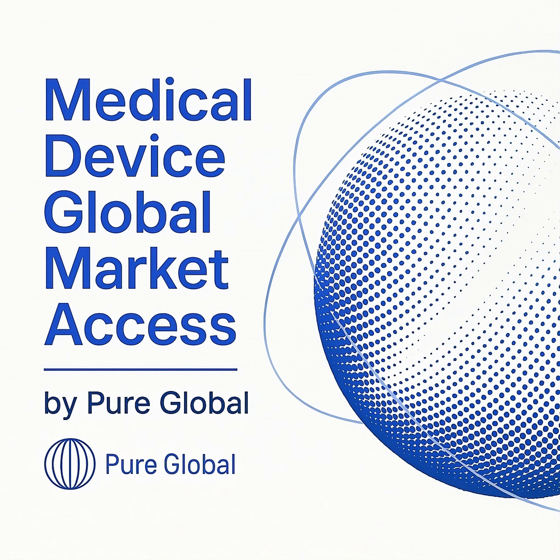A crucial requirement for obtaining an MDL for Class 2, 3, and 4 devices is a valid Quality Management System certificate that conforms to ISO 13485:2016. This certificate must be issued by a recognized auditing organization under the Medical Device Single Audit Program, widely known as MDSAP. While your FDA-compliant quality system is robust, it must specifically be MDSAP certified for Health Canada to accept it. This is a non-negotiable prerequisite.